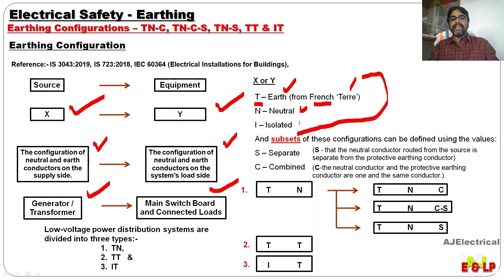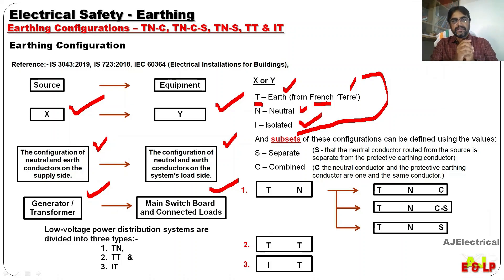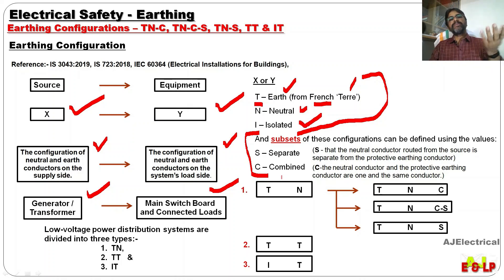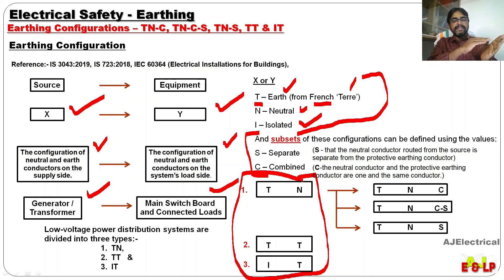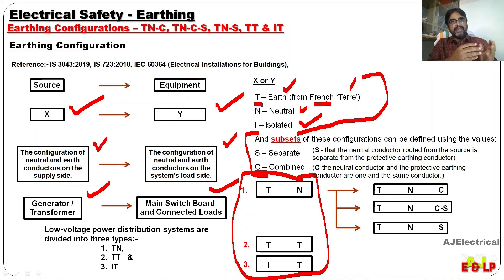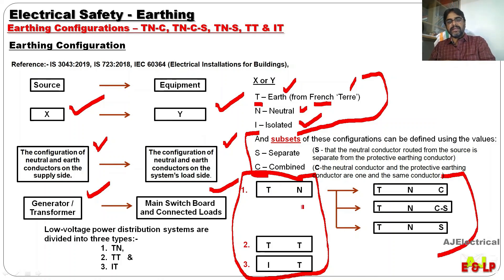N means neutral. S means separate and C means combined — these are subset notations. The basic earthing configurations are: TN system where the source side is T and the load side is N. The TN system is further divided into TNC, TNCS, and TNS — describing how the neutral and earth conductor come from source to load. Other than TN system, there is TT and IT. We will study each in detail in subsequent videos.